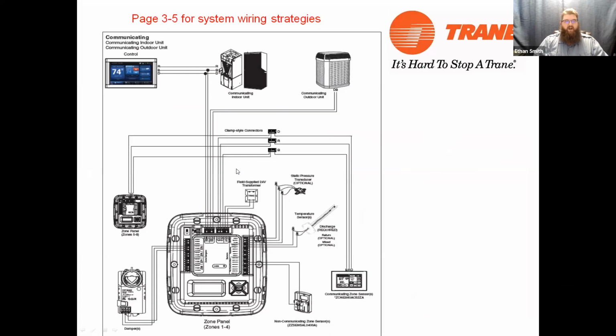They give you all kinds of wiring diagrams in there. This would be for a fully communicating unit. So this would be a communicating indoor unit, communicating outdoor unit. We're going to have R, D, and B from the thermostat to the indoor equipment. And we're going to have data and common only from the indoor unit up to the zone panel. We do not bring R from the indoor equipment to the zone panel. The zone panel is powered independently from your field supplied 24-volt transformer.